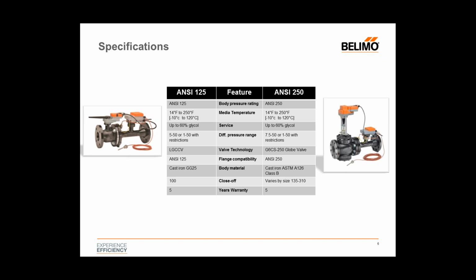The differential pressure range has a little bit of variation. It requires a little bit higher differential pressure with the ANSI 250. So it's 7.5 to 50 psi differential as opposed to 5 to 50 psi differential with the ANSI 125 versions. They can also operate at a lower differential pressure. That is one of the things that makes a pressure-independent, electronic pressure-independent solution unique in the marketplace, giving that flexibility to operate at lower differential pressures.